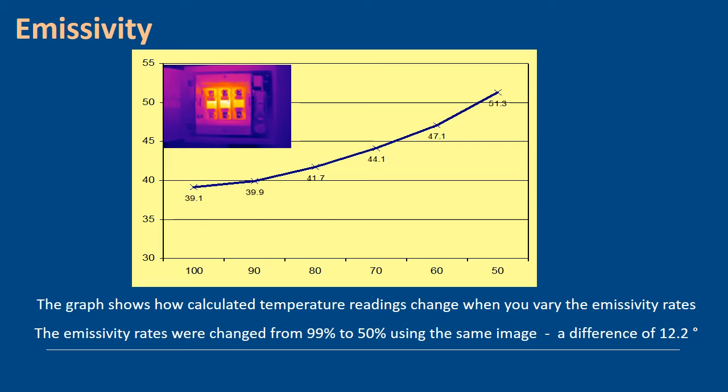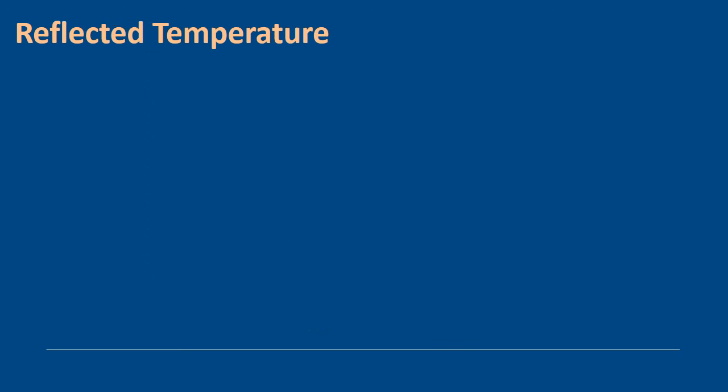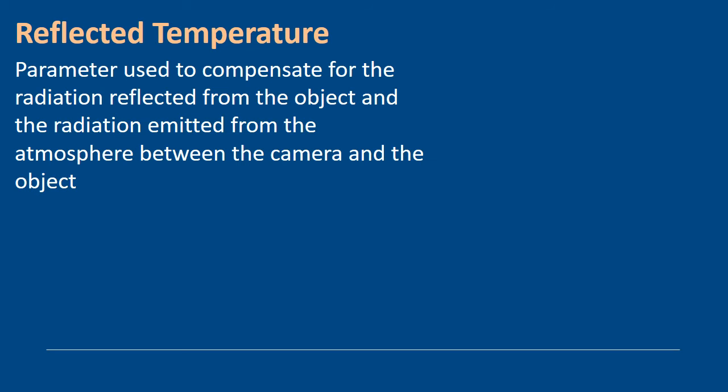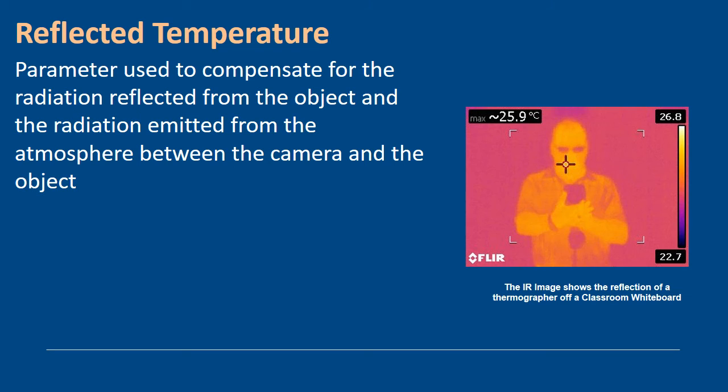When we then understand reflection, we spoke about when I looked at Kirchhoff's law a few slides ago, we showed that reflection and emissivity are inversely linked. So whatever I do to one affects the other. When we look at reflected temperature, this parameter is used inside the camera to compensate for radiation reflected from the object and the atmosphere between the camera and background objects.